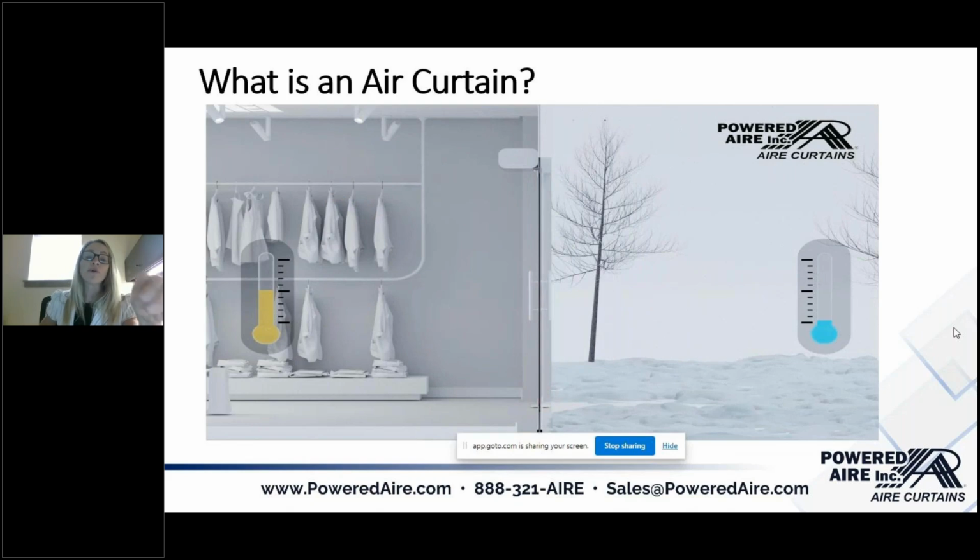So one thing I want to point out, most of the air curtains that we provide will be provided with something that's called a time delay relay. What that does, once that door closes, the air curtain will remain on. I think it's factory set at 30 seconds, but that is adjustable. Just in case it's a high traffic area, that air curtain will not cycle on and off 1,000 times throughout the day.